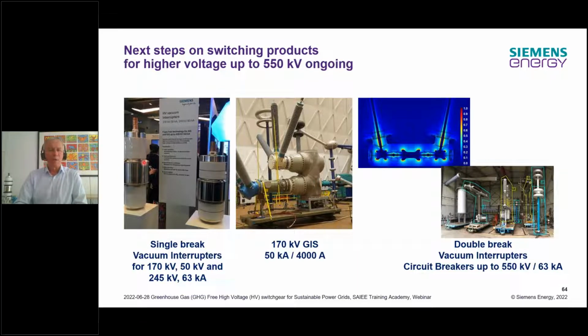How is that done? On the left-hand side you see the vacuum interrupters - on the right side is the 170 kV, 50 kA vacuum interrupter, and on the left-hand side is the 245 kV, 63 kA. That was presented in Paris in 2018. So this is a development.